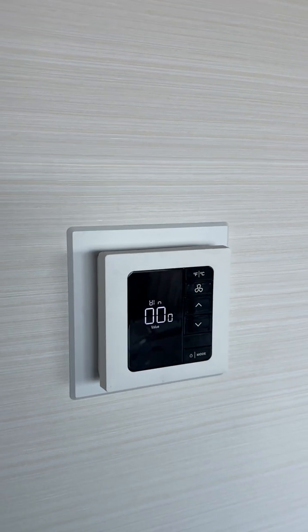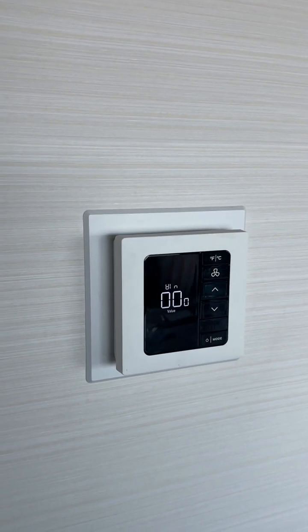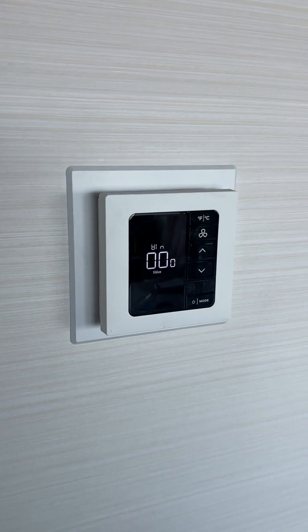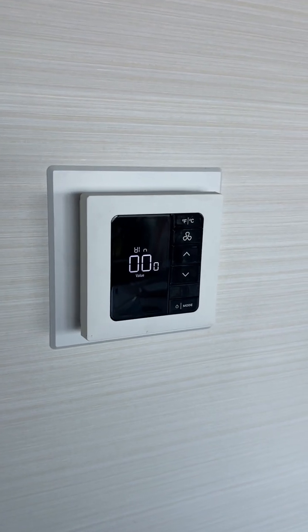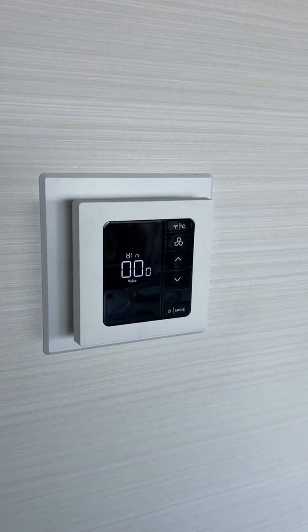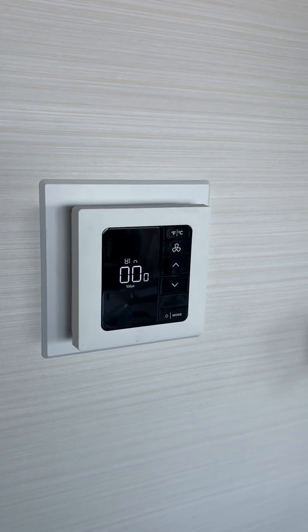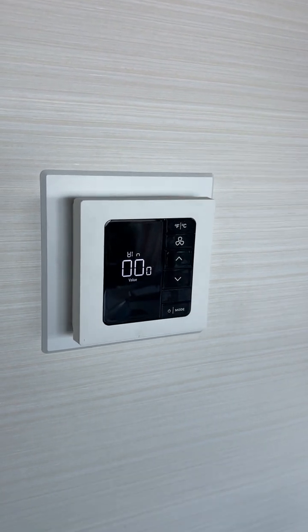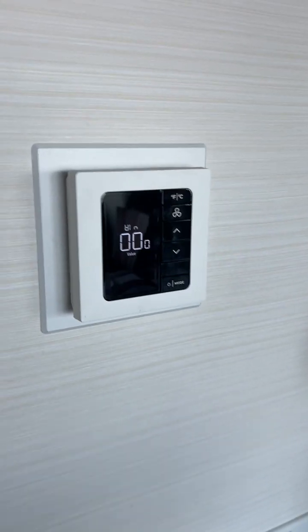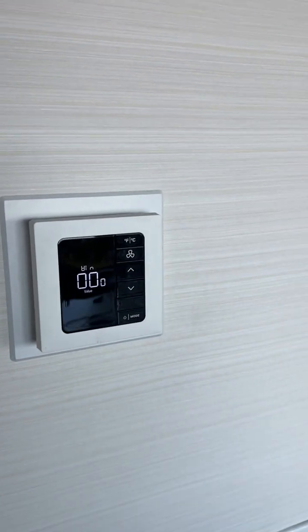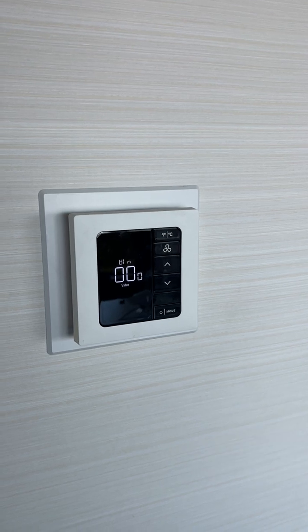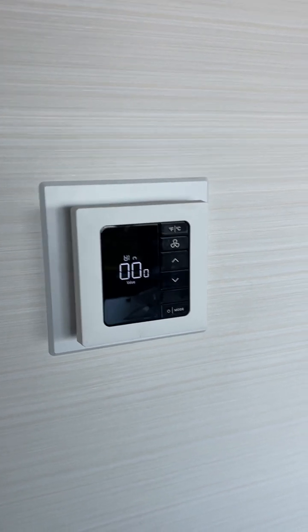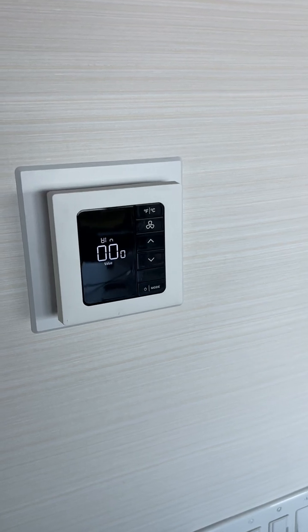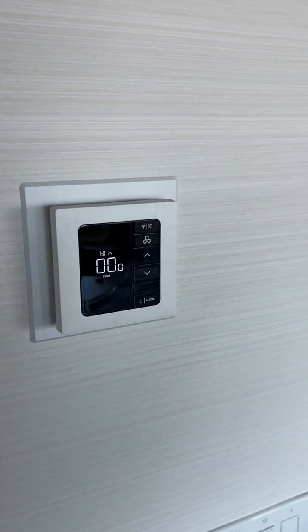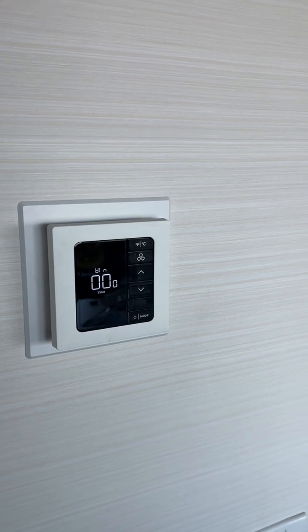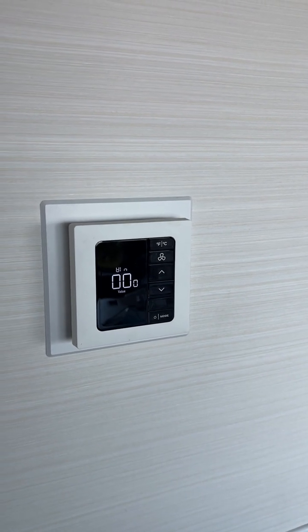Also, if you put the thermostat in VIP mode, which is also referred to as EMS light or limited energy management mode, which I'll show in a minute, it will disable the balcony sensor while it's in that mode. That mode lasts for 72 hours or until check out once your property management system is live. So that would be a good way for troubleshooting, like if we have someone in the room. It's good to be able to do some bypasses. That'll limit the unoccupancy bands to within 1 degree, but you shouldn't leave it like that forever. It expires either after 72 hours or check out, depending on whether your property management system is connected or not.